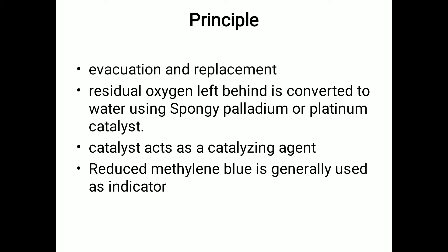The residual oxygen left behind is converted to water using a spongy palladium or platinum catalyst. The catalyst acts as a catalyzing agent causing slow combination of hydrogen and oxygen to form water. Reduced methylene blue is generally used as an indicator — it becomes colorless under anaerobic conditions but regains its blue color on exposure to oxygen.